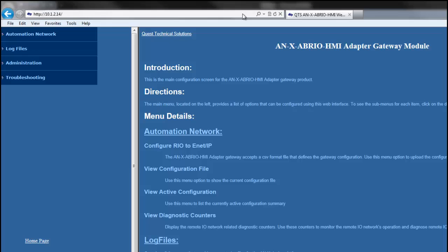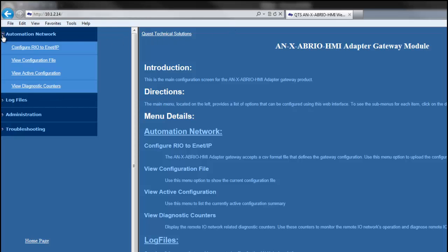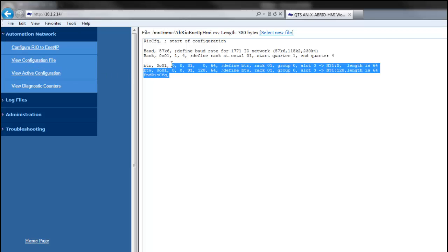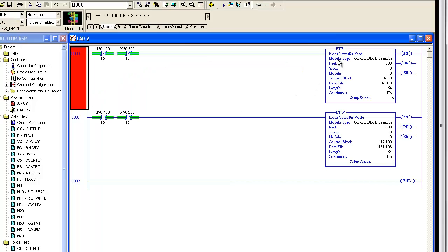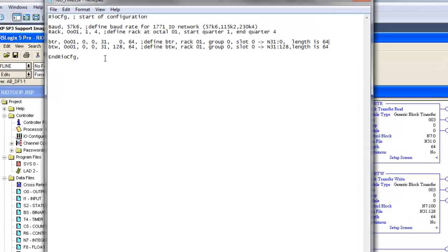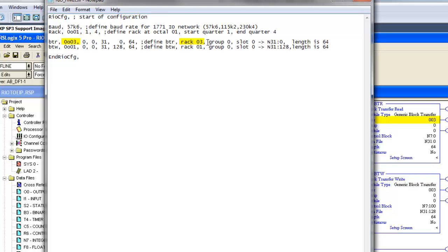Now we're going to configure the RIO side of the gateway with a CSV file found on the CD or on the website. If you don't have the CD or internet access, you can copy the sample configuration out of the module by clicking on View Configuration File and copying it into a Notepad file. We need to see the existing BTR and BTW — that's block transfer read and write values — going to the original HMI and mimic it in the CSV file. The BTR is rack 3, group 0, slot 0, reading into N31:0 for a length of 64.